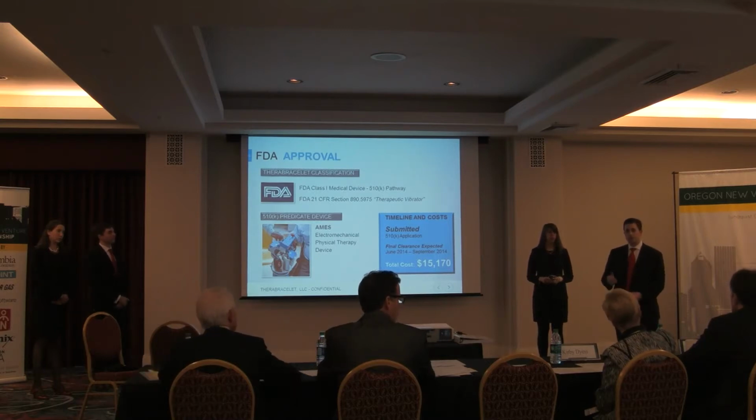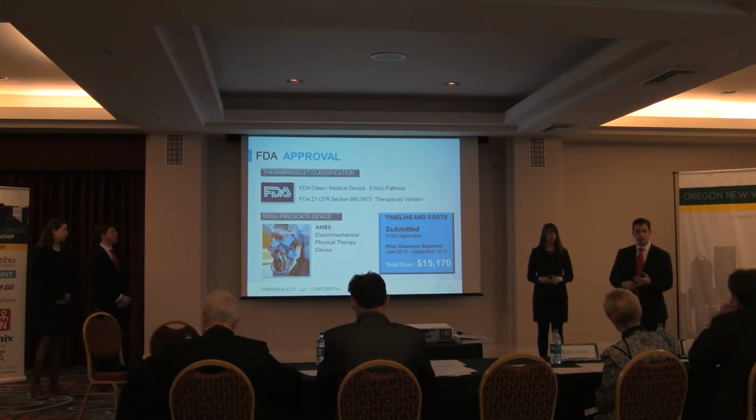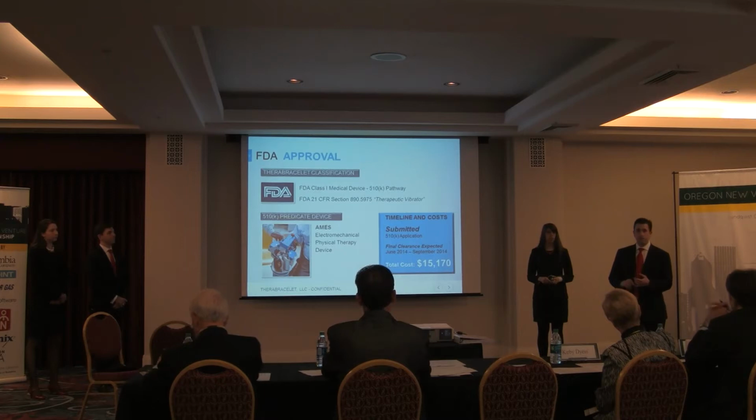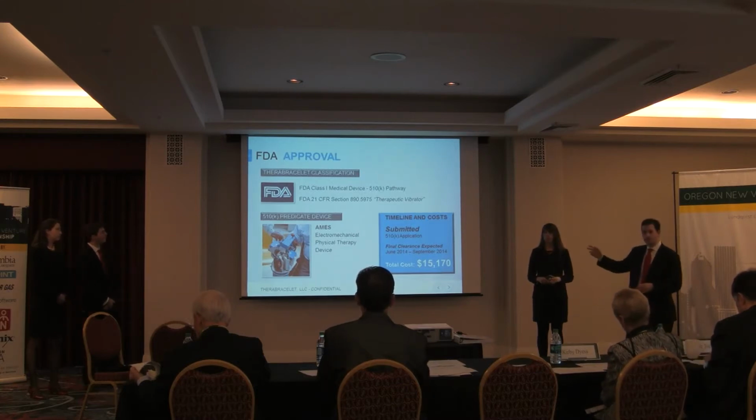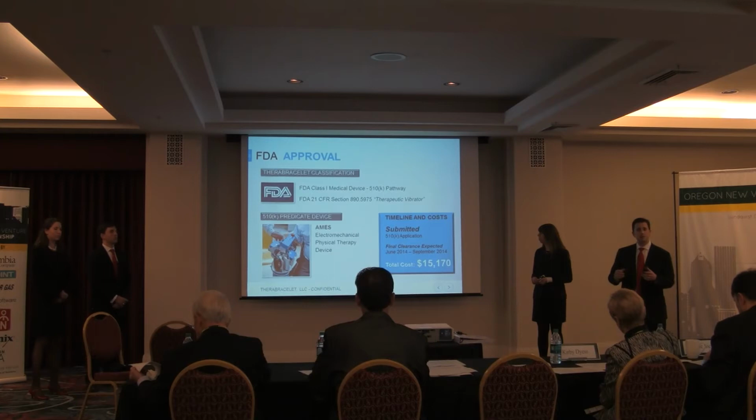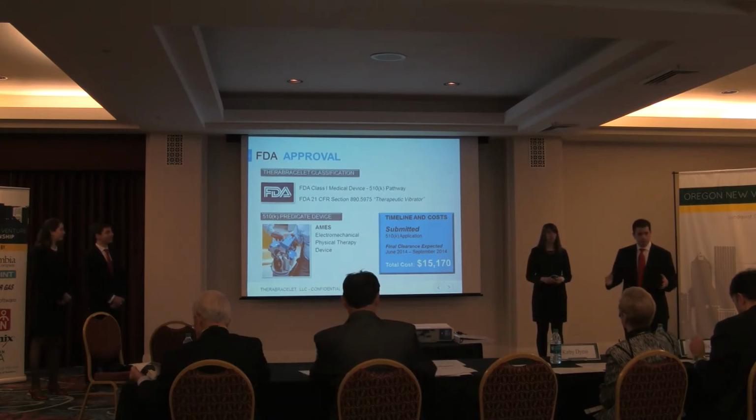We used Dr. David McClure, who's a seasoned regulatory consultant. He helped to identify our device as a Class 1 510(k) medical device. This was fantastic news for TheraBracelet and our investors, as it represents the most straightforward pathway to achieving regulatory approval. He also helped us identify our predicate device, which was the Ames therapy device. Because we have a predicate device, we will not be going through lengthy clinical trials.